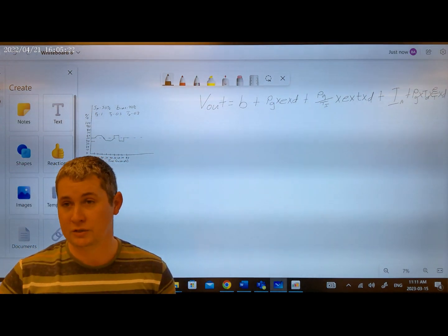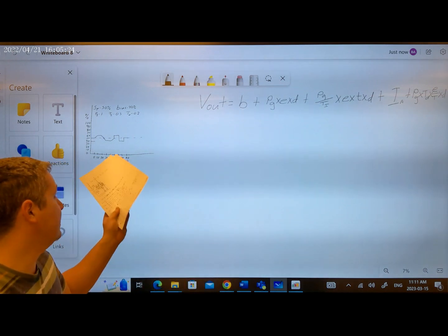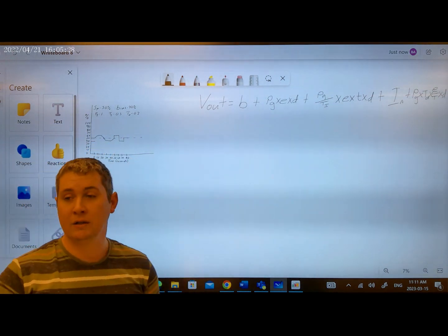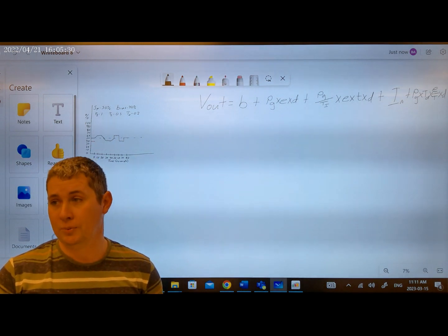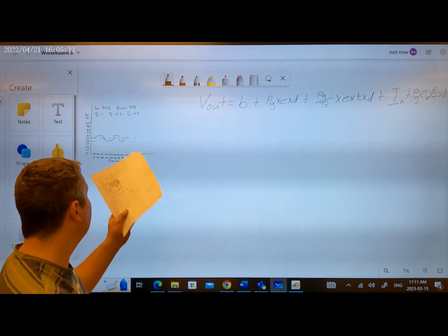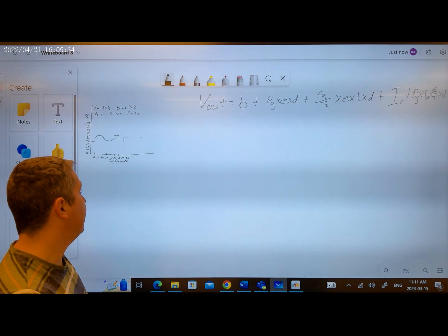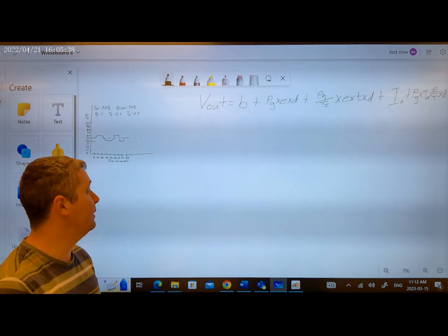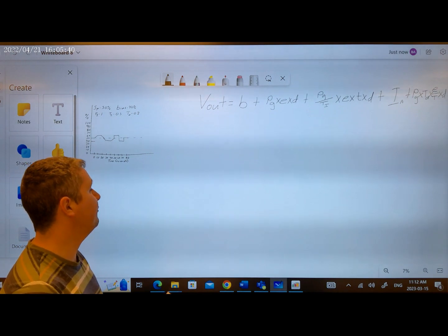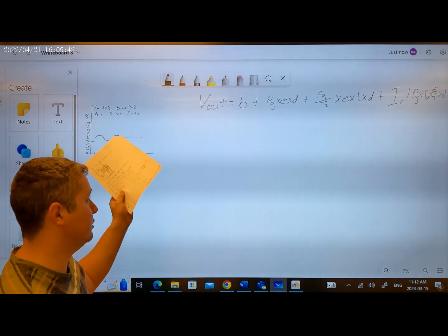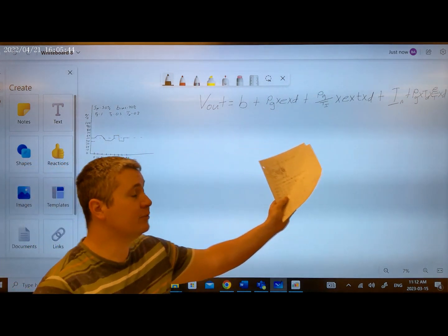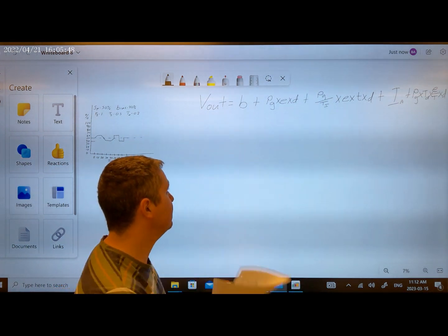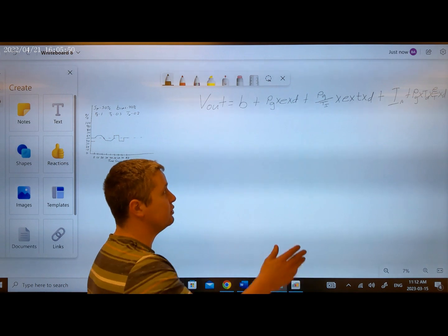our PID control. So we're going to have this as our process variable, the black line. The red line will be our output of our controller. We have a set point of 50, a bias of 40, proportional gain of 1, integral of 0.5, and derivative of 0.2. Our equation, which seems quite long, but yet we've simplified it because we know that we have different sections to this.